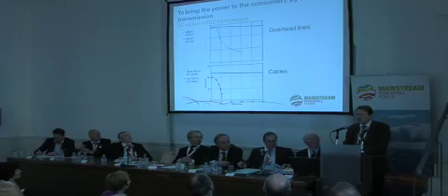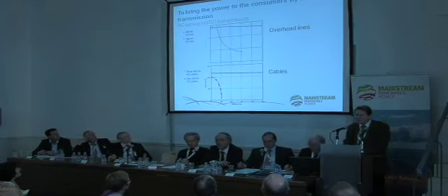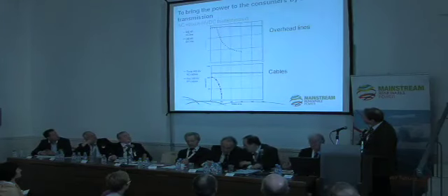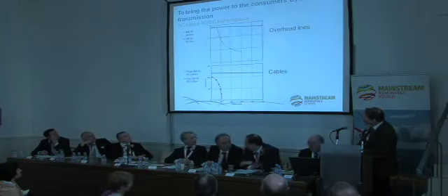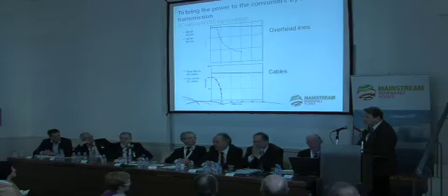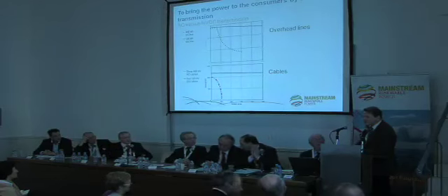First, why do we talk about HVDC when we have HVAC, alternating current? Most of the transmission is done by alternating current. But you can see on the upper graph, comparing transmission over long distances, the blue line is HVDC, and the dotted red one is AC. AC has limitations when the distance is longer. Above 600 kilometers in a single AC line, it can't basically transmit anything at all.